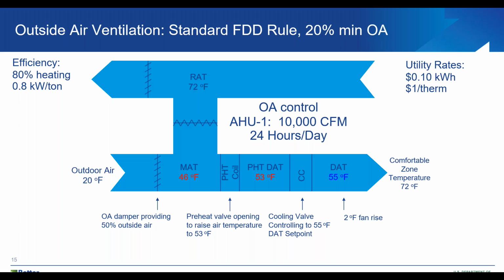So this would normally be flagged as a damper problem or based on the mixed air temperature. And as a result of it, the preheat valve is opening to increase the temperature from 46 to 53 degrees. So they're using extra heating energy as a result of this. So under normal conditions, you would have this flagged as an economizer related problem.